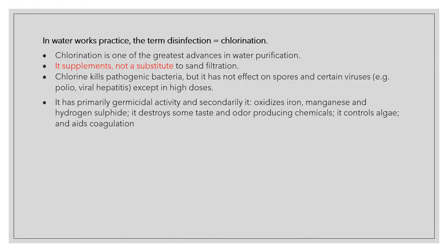When it comes to disinfection, just think chlorination. Reason being that chlorination is one of the greatest advances in water purification. It's going to supplement and not substitute sand filtration. Chlorine is going to kill the pathogenic bacteria. However, it does not have effect on spores and certain viruses except in high doses. Its properties are that it primarily has germicidal activity, and secondarily, it oxidizes some metals, it destroys some bad taste and odor producing chemicals, it controls algae, and it aids in coagulation.